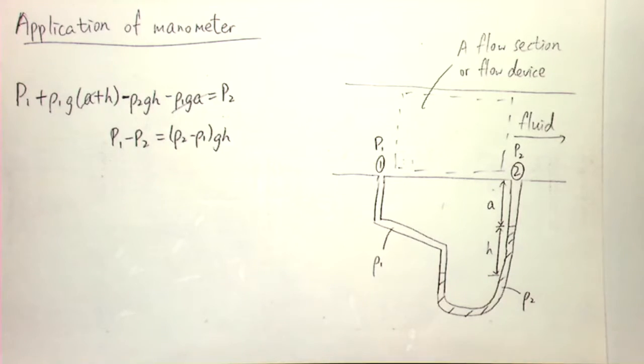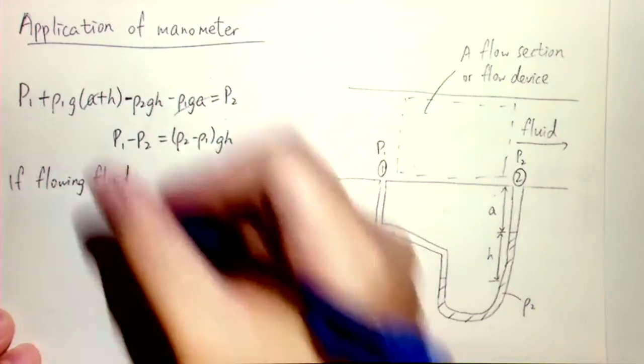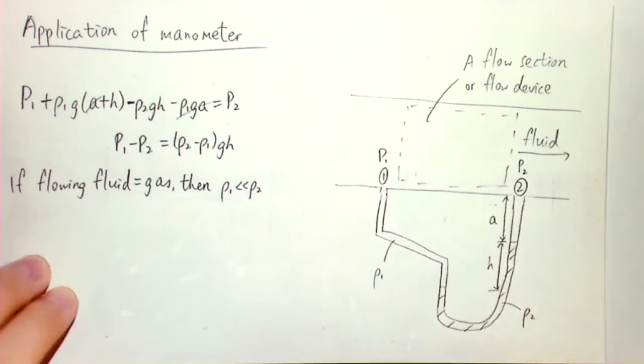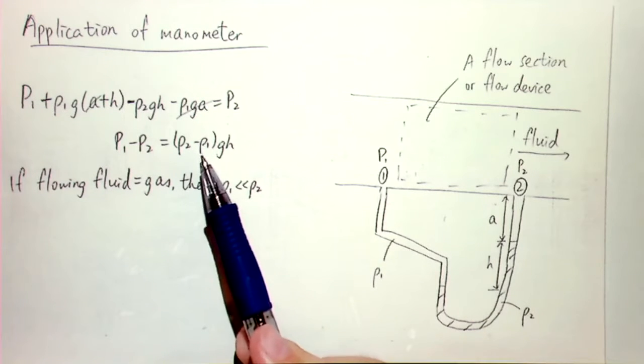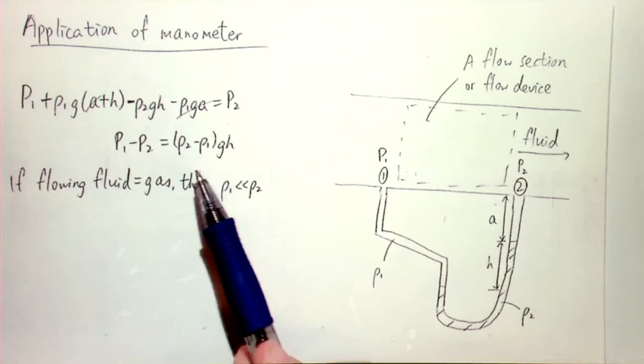If the flowing fluid is a gas, for example in an air duct, then rho 1 is much smaller than rho 2. Because inside the manometer we use a liquid as manometer fluid, rho 2 minus rho 1 is approximately equal to rho 2. So the equation simplifies further to approximately rho 2 times g times h.